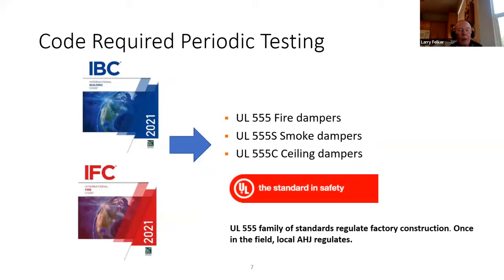Now, those two codes refer to UL standards, the UL 555 family of standards for new construction, factory installation, what actuator can be used on what damper. But once the dampers leave the factory, except for the framing and following the directions that the damper manufacturer includes, the local authority having jurisdiction is in charge of the dampers.